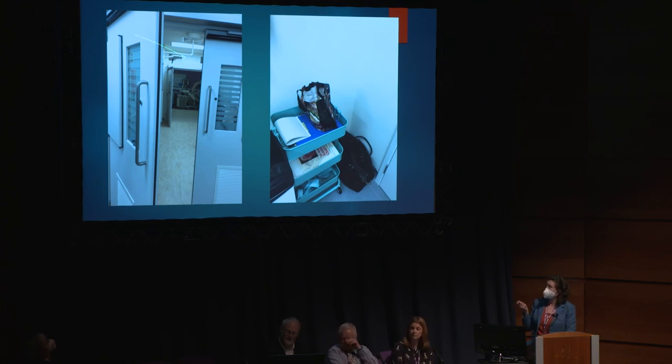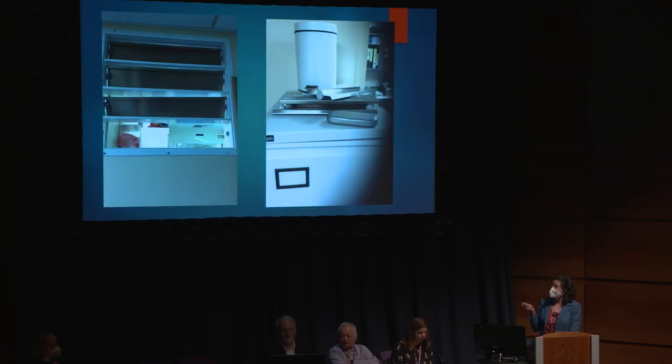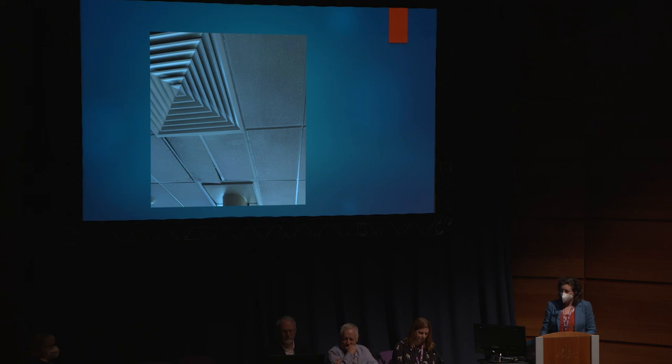This was a theater suite that had doors opening and closing constantly because they were set incorrectly with no automatic closers when there should have been. Another older theater suite - I counted 20 baffles that were missing or stuck. What's a baffle? It helps decide where the air goes when it should go. I found them on top of a fridge. As Malcolm Thomas said to me: if you're given a car and you can have one without one wheel, is that going to do any good? No. A ventilation system is a system - the component parts working together. We have to give the same importance to every aspect of it, not just say the air handling unit passed its validation when you've got all the baffles sitting on a fridge.